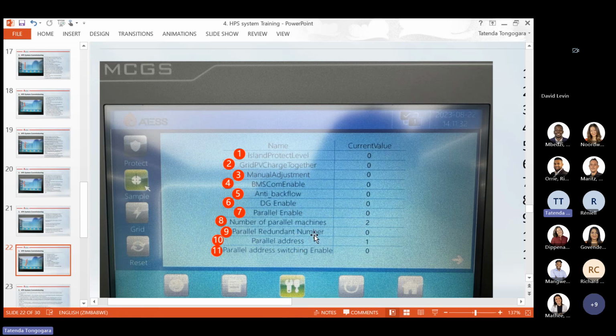And then we have parallel redundant number. You can set this one to 1. So in the event you have a parallel system, 2 machines, you can set parallel redundant number to 1. So in the event that one machine goes into fault mode, the other machine will take the load, but your load should be lower or equal to the size of your one inverter. So if you have 2 HPS 100 in parallel and the load is 110, the whole system will trip.